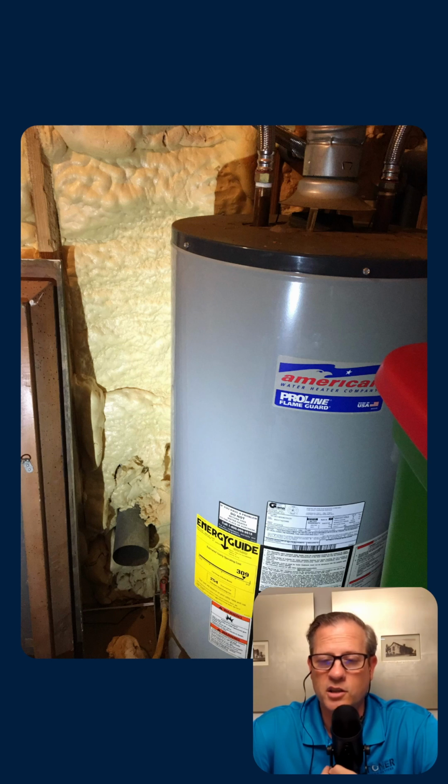Carbon monoxide is a real thing. That makeup air below, that only works if you create a convection loop. So you'd have to have one down low and one up high. Even then, it's attached to the outside. And those pressure dynamics, most likely what would happen is both of them would intake instead of create a circulation vent. It's just not safe.